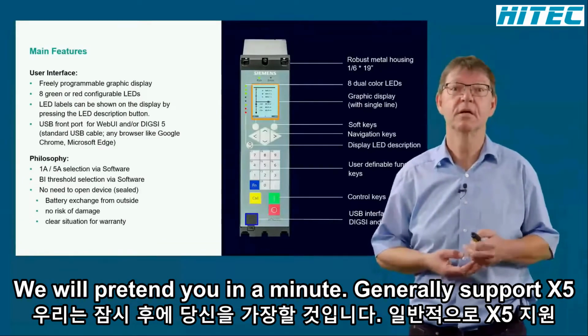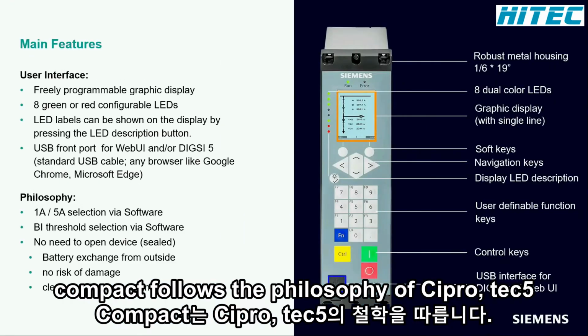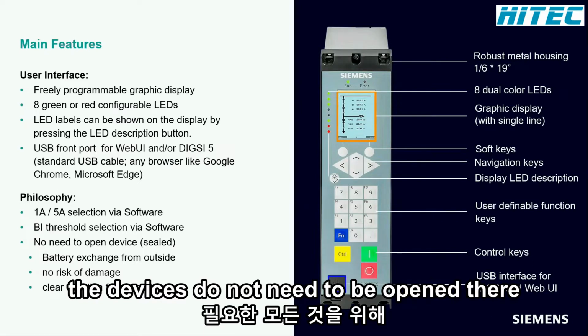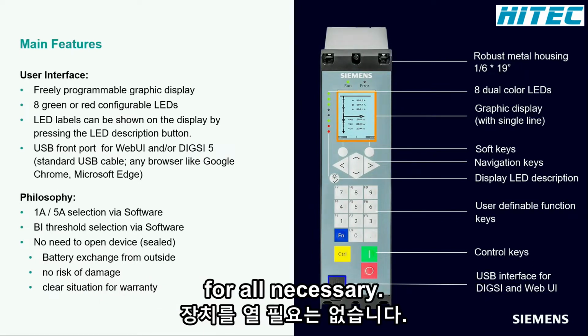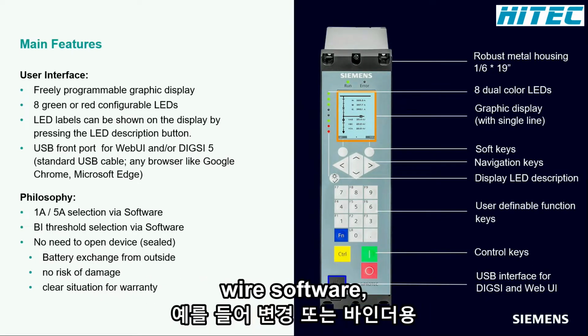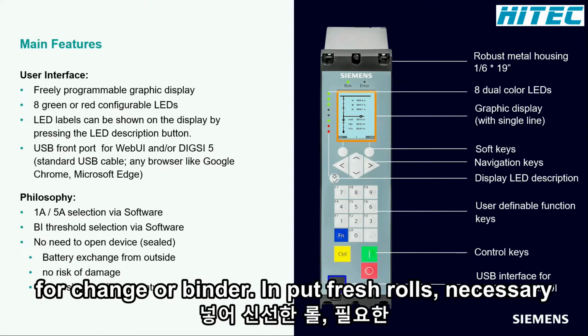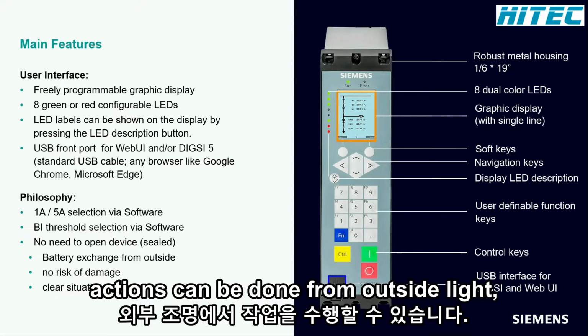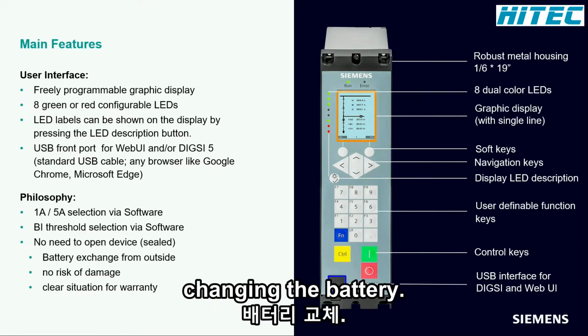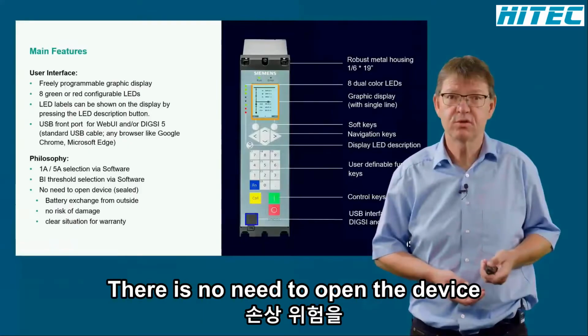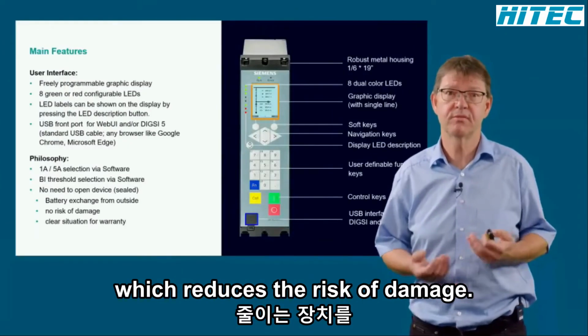Generally, SIPROTEC 5 Compact follows the philosophy of SIPROTEC 5. The devices do not need to be opened. Therefore, all necessary handling is done either via software, for example, for changing the nominal current or binary input thresholds, or the necessary actions can be done from outside, like changing the battery. So there is no need to open the device, which reduces the risk of damage.